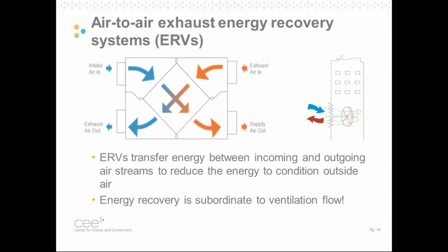If we can transfer air from the exhaust streams, we can meet some of that load and reduce the amount of energy we have for heating and cooling ventilation air. This is about ventilation air. Energy recovery systems don't heat and cool buildings. They treat ventilation air. So we say that energy recovery is subordinate to ventilation flows. We have ventilation flows for very specific reasons, and we should do our best with energy recovery to reduce the energy requirements of those ventilation requirements.